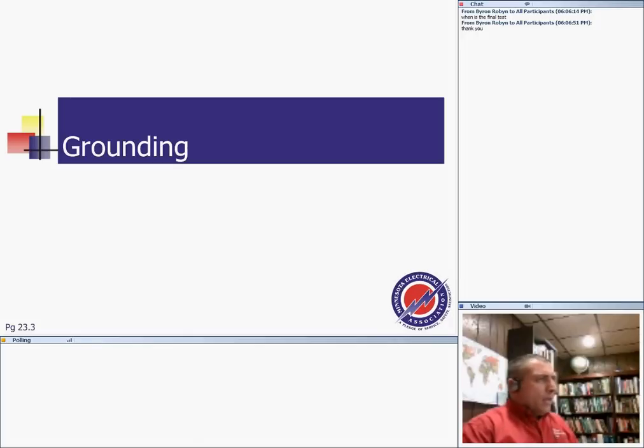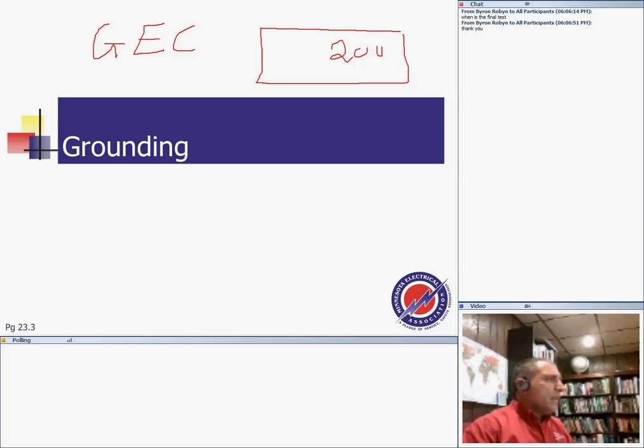Okay, grounding. You guys will study grounding if you come to one of my grounding classes. We go into details on that. I want to make sure that you understand a very, very important concept. Concept number one is the grounding electrode conductor. Grounding electrode conductor is the one that takes the service, and let me just draw my service. Here's my 200 amp service, here's my neutral over here. And here's my ground, right?